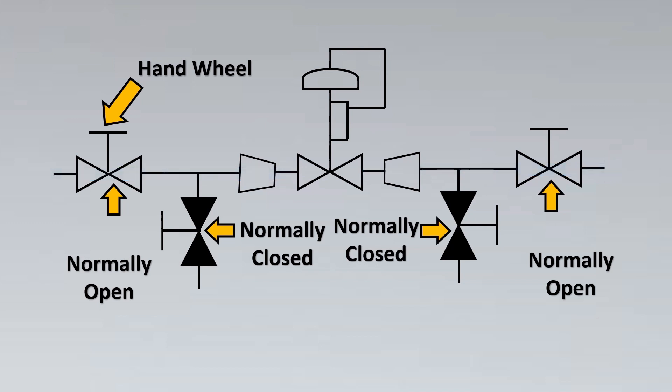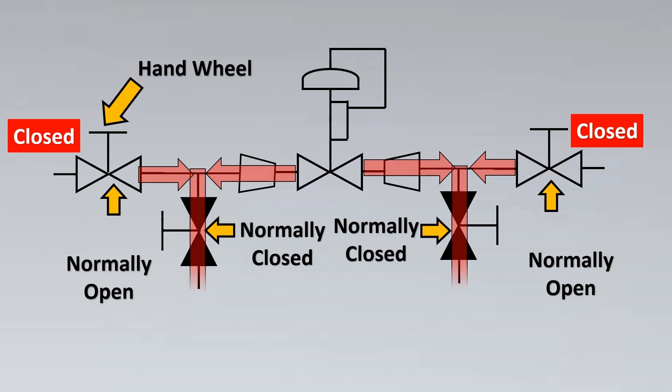Once we close these two valves, there is fluid which is stuck in between, right? So in order to isolate the control valve, then we will have to drain it off. So these normally closed valves then will be opened and that would drain all the liquid out, and then we can safely remove the control valve out from the service.